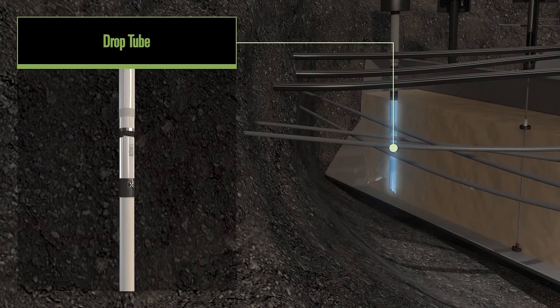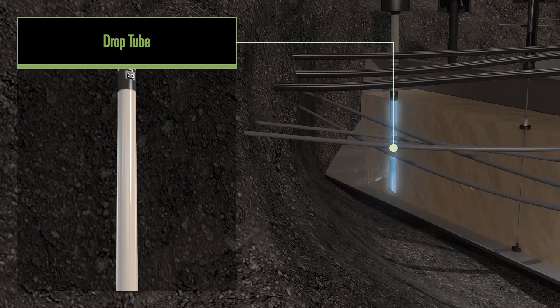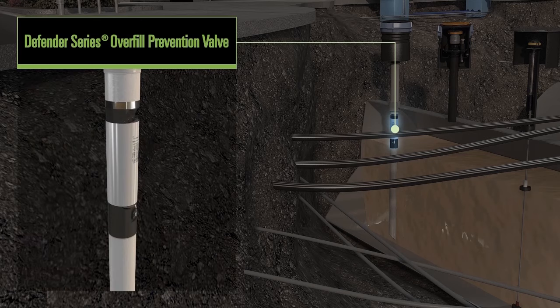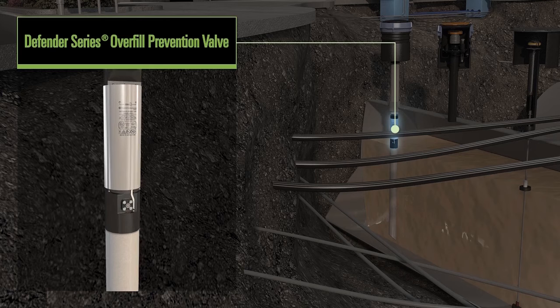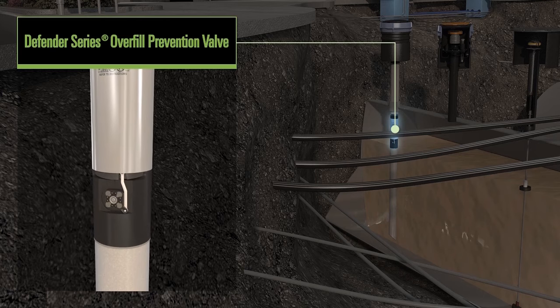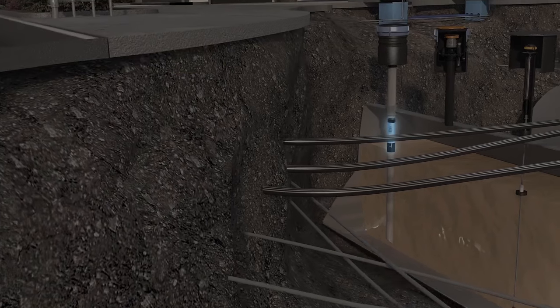The fuel flows through the hose into the drop tube and into the underground storage tank. An overfill prevention valve monitors the level of fuel in the tank and utilizes a float shutoff mechanism to stop fuel delivery once the tank is at 95% volume to prevent an overfill of the tank.